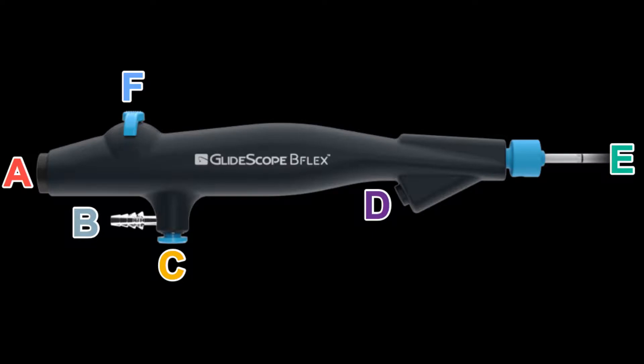We're going to go over essentially the anatomy of the new bronchoscope. The disposable part of the bronchoscope will be the handle and the fiber optic camera, which comes in a long vertical plastic packaging and will be kept next to the GlideScopes. There is also a non-disposable connection cable, which serves as both the fiber optic and power source connection for the disposable scope to our existing GlideScope screens. These cables connect to a portal at the back of the GlideScope screen and then attach into part A on both the vertical and horizontal diagrams of the disposable bronchoscope.